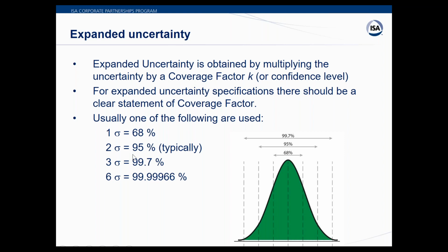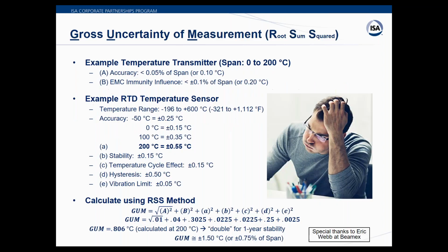And one way to do that, Roy, like on your test, you did a 3-point check. But you could do it a second time. You could do two cycles of a 3-point check. True. Or you could do three. The more data you have, that's how you get to this higher confidence level. So if you see the same thing three times, obviously your confidence level is going to get up into this area here. But who has time to check something three times? In our world, the first time's good enough. It's representative of how that transmitter's acting. That's true. And it's not just time, it's money.